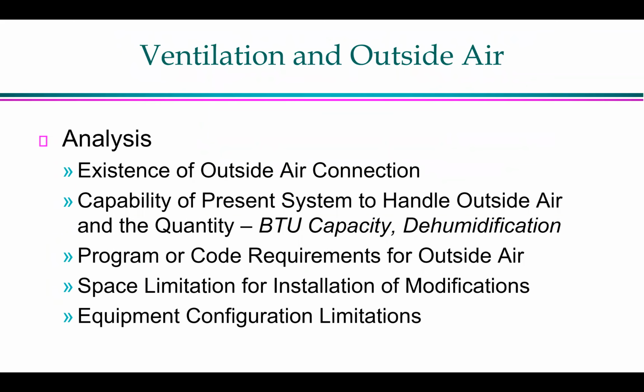So next. Ventilation analysis. You have to take a look at your outside air. Can you increase it? Does the outside air connection exist? If you're using a lot of small split systems in some buildings like schools, you can't increase the outside air. What is the capability of that system to put in more outside air? Because you can't just totally open the outside air vents on some systems, because the units aren't designed to handle that. So you need to go back to the design level and see what's capable.